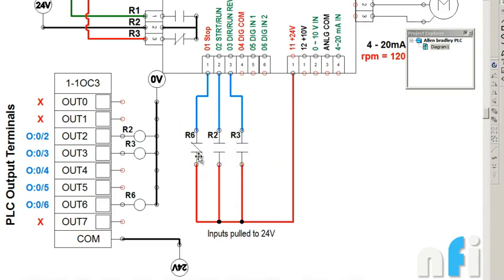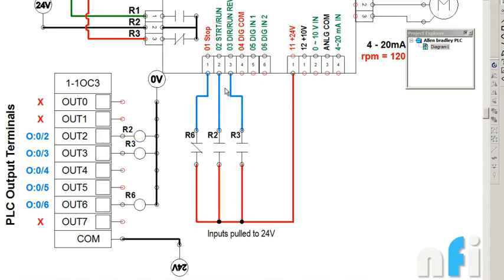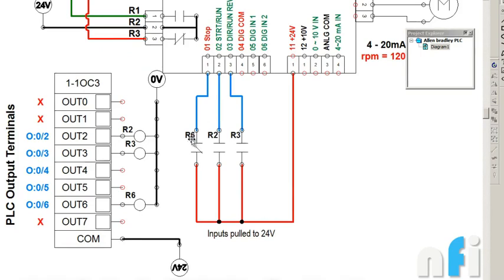Our O:0/2, this is the output. If this gets on, your auto relay R2 will be on and this will close the contact between 11 and 2. If this happens, this will start the drive. When you provide 11, when you connect 11 to 2 just for a moment, just for a pulse, it will latch the drive. That's the three-wire. When you disconnect 01 and 11, it will stop the drive. And when you provide signal from 11 to 03, it will change the directions.